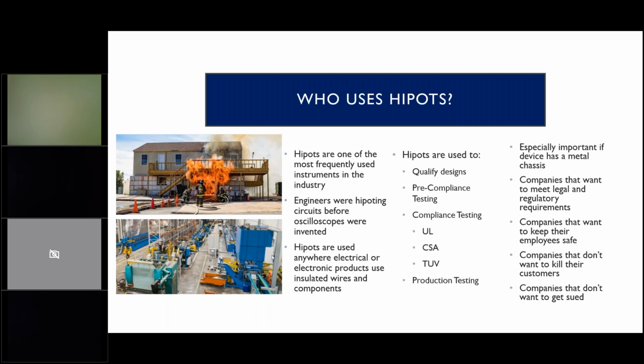HIPOTs are used anywhere electrical or electronic products use insulated wires and components. If you see a factory like this, probably there's HIPOTs in there, checking everything that's going on. In addition to that, you should understand that HIPOTs are used to qualify designs. They're used for pre-compliance testing and compliance testing. So if you go to a test house like UL or CSA or TUV, they probably use HIPOTs in their testing. And you can actually get your own HIPOTs and do your own testing in-house so that you know when you get to the test house it will pass.